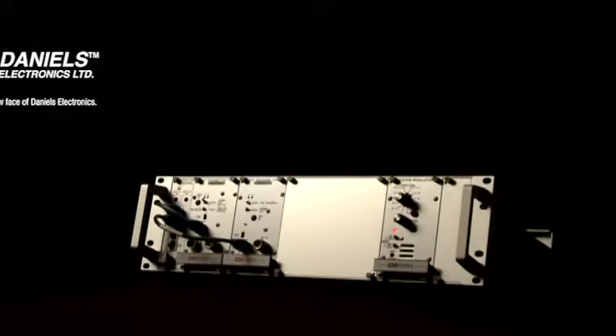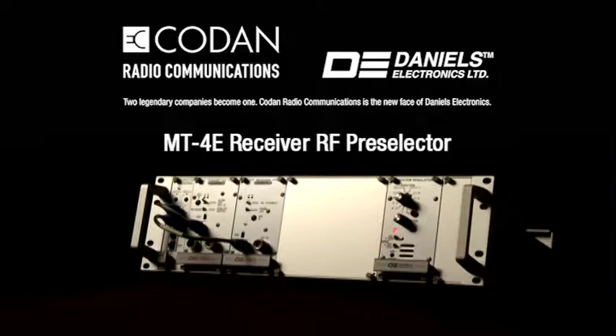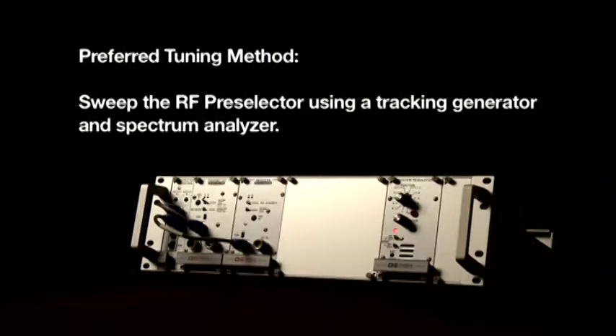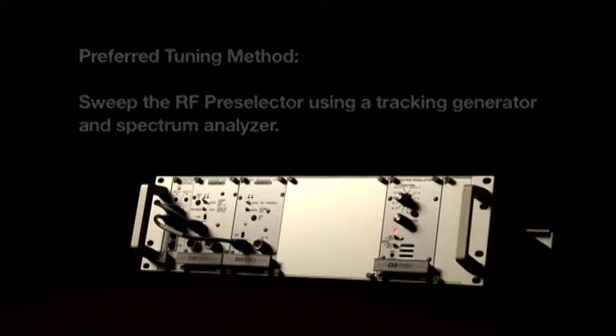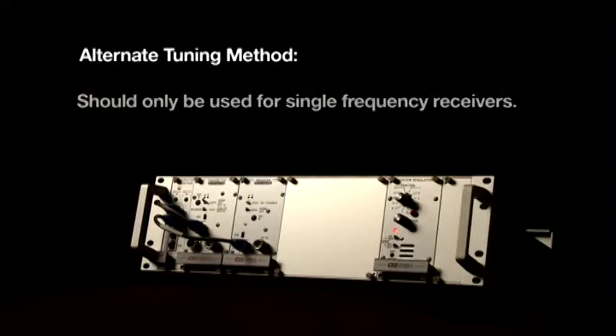This video will describe how to tune the Daniels Electronics MT4E receiver RF preselector. The RF preselector may be tuned several different ways. The preferred method is to sweep the RF preselector using a tracking generator and spectrum analyzer. The alternate method is to tune the RF preselector for best SINAD response. The alternate method should only be used for single frequency receivers.